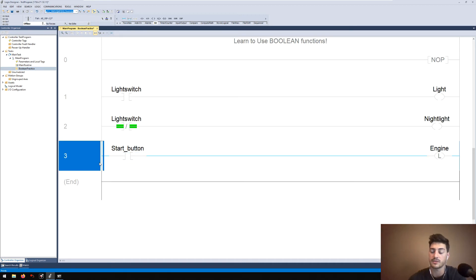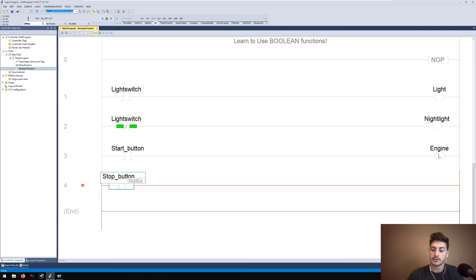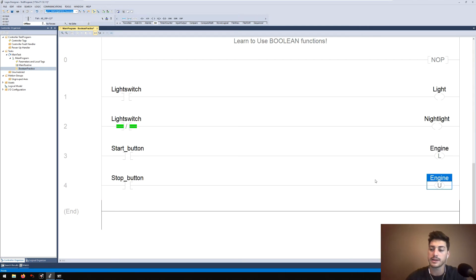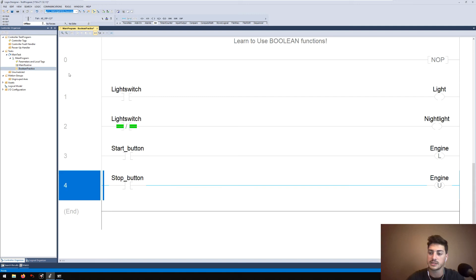There are instructions called OTL and OTU — Output Latch and Output Unlatch. When you push the start button, you latch the engine — make it a one, make it true. When you release the button, there's no code currently making the engine stop, which is exactly what you want. Then, when you push the stop button, the associated OTU command turns the engine off. So with OTL/OTU pairs: when the start button is pressed the engine turns on, and when the stop button is pressed the engine turns off.